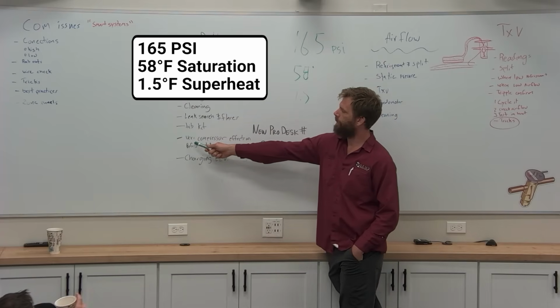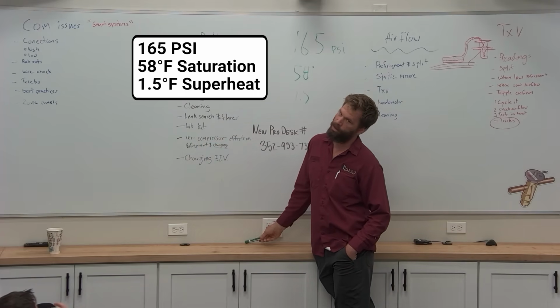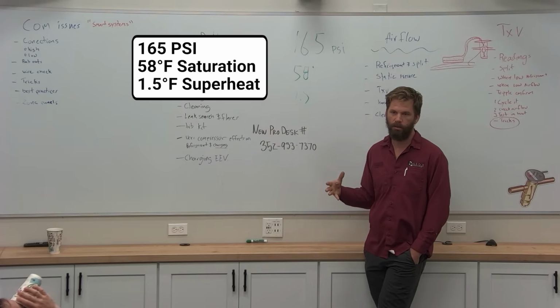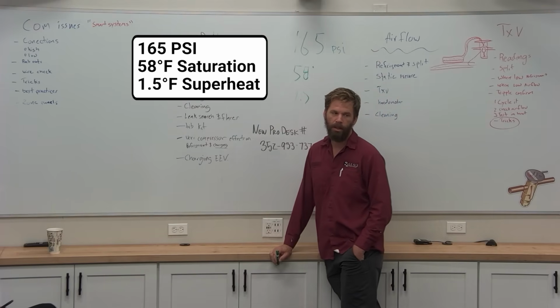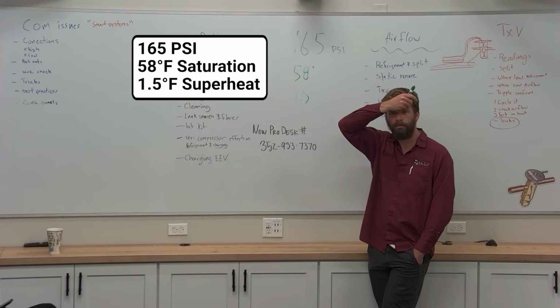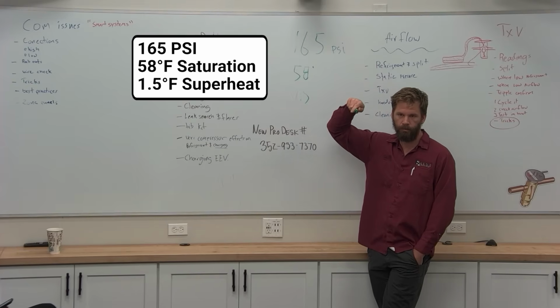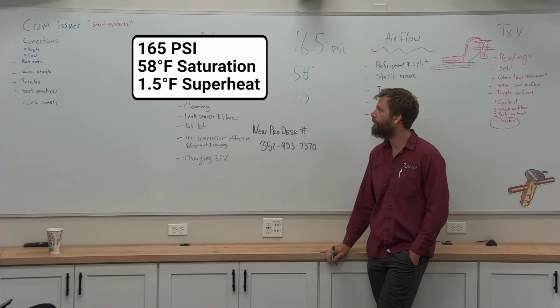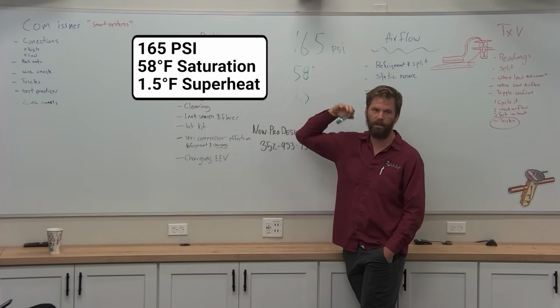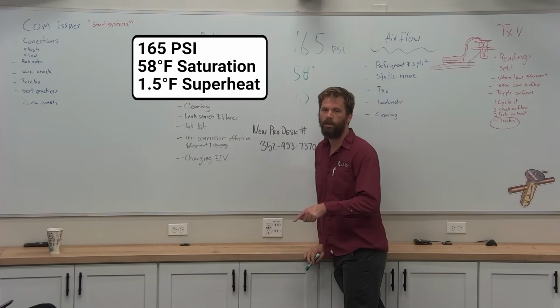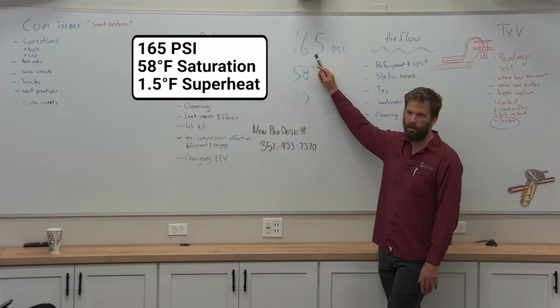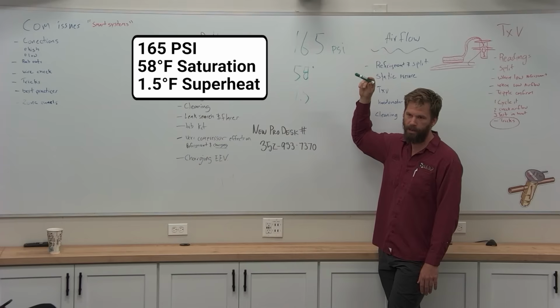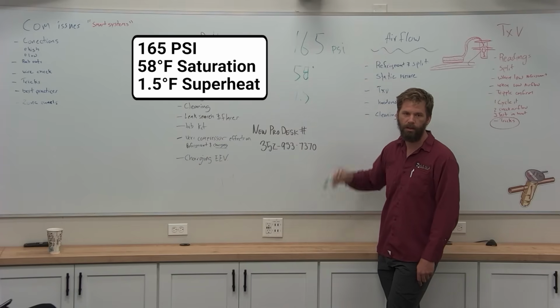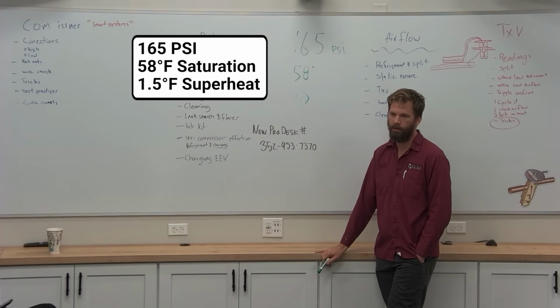Yep. You have a variable speed compressor, and that affects refrigerant and charging. Your compressor adjusts based on load or based on demand. So in this situation, he had the temperature down, but the customer had set their fan speed to super quiet. So the inside fan is running really low, and that locks the compressor from going into full speed, otherwise it could freeze. So they have this little backward safety where if the fan's in low speed inside, the compressor can't run full speed. So if your compressor is running in a lower stage, suction pressure is higher, coil temperature is higher. He bumped the fan speed up, dropped the temperature down, and immediately we got to our nice 28-degree split, everything running great in the system.